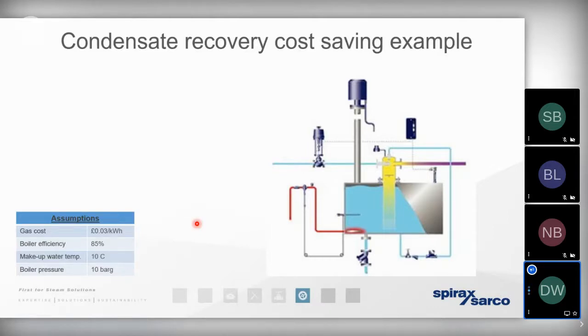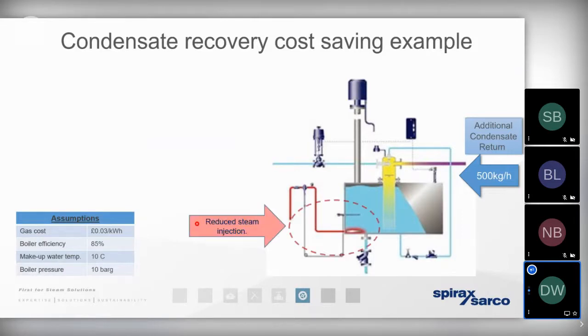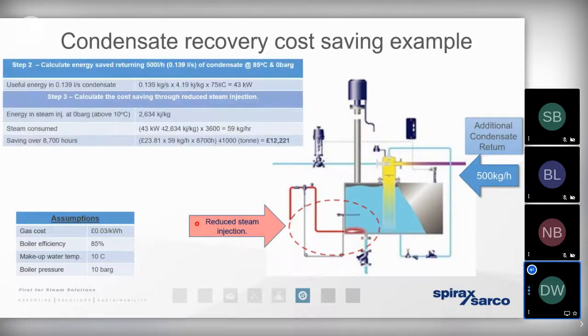If we're able to calculate how much condensate we can now recover, we know how much condensate we can get back to the feed tank. So that means that we're not only increasing the rate of condensate return, but we're also reducing the amount of direct steam injection that we were previously using.